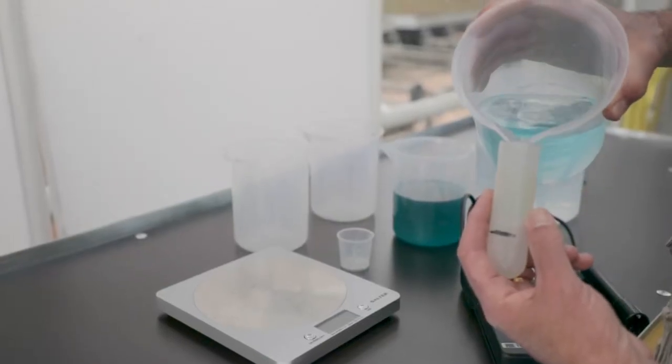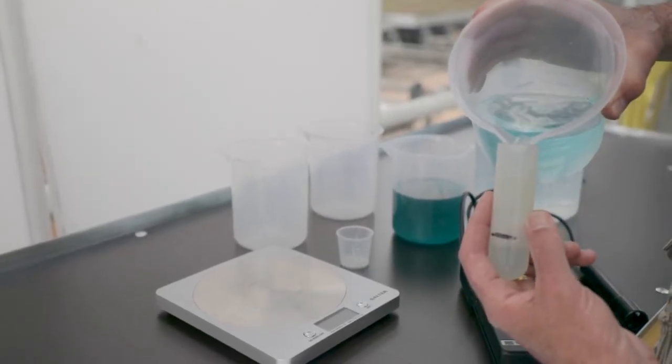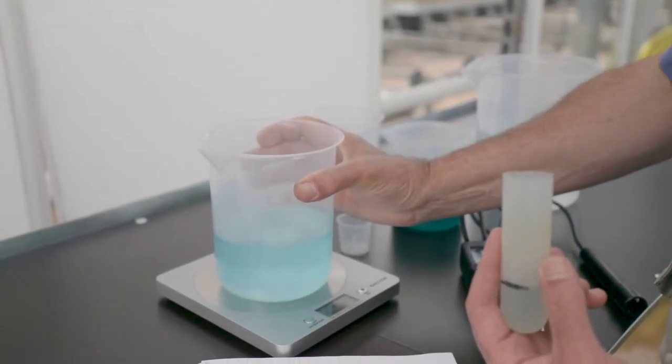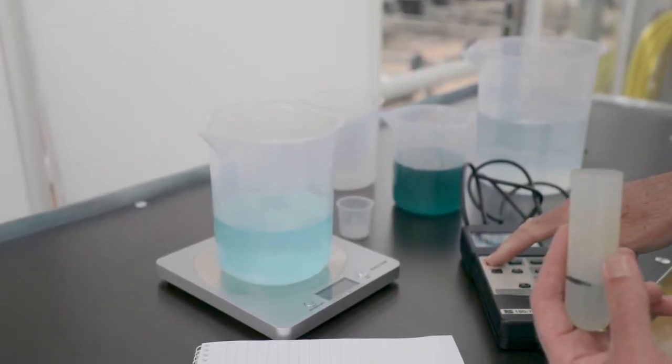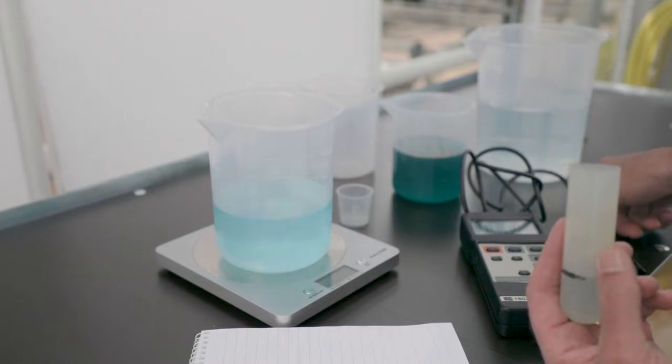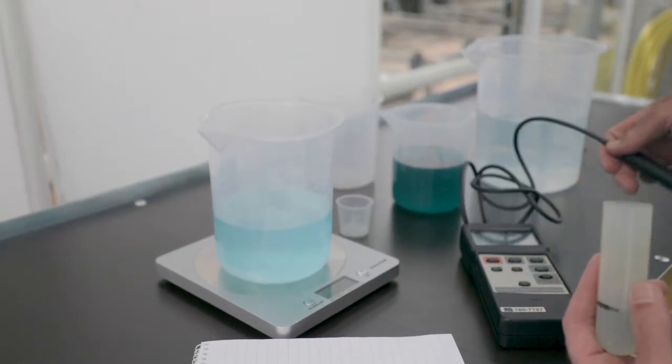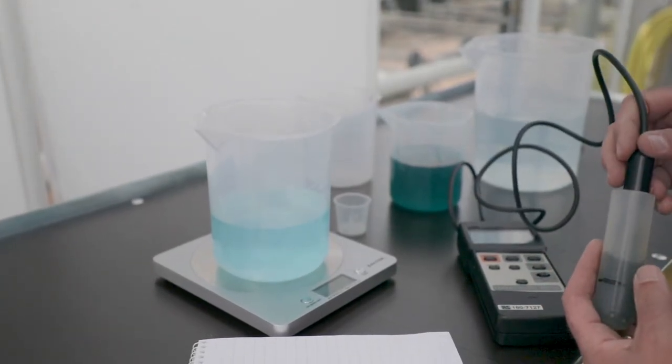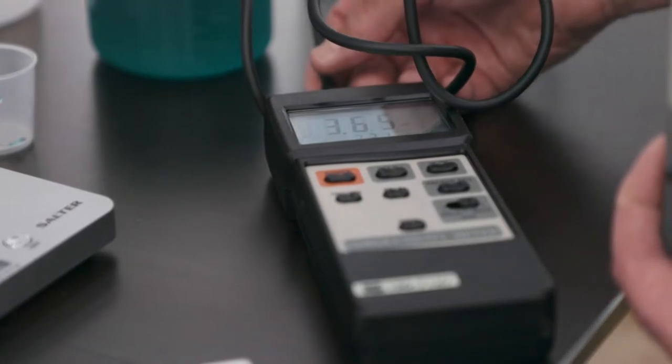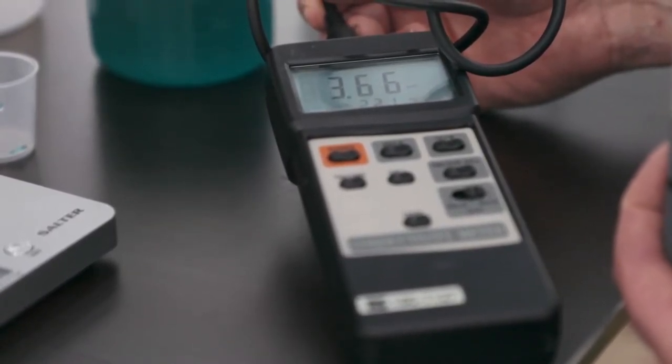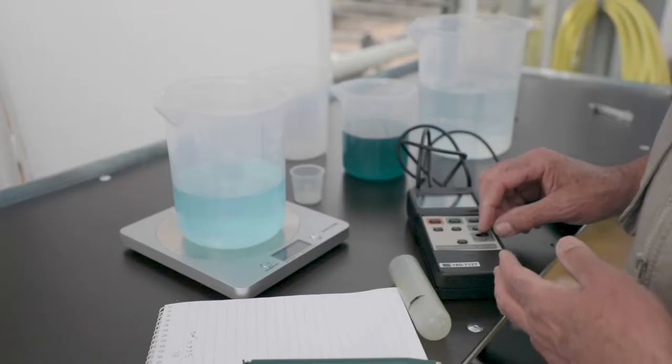We now have a one in fifty diluted solution and what we're going to do now is just measure the conductivity of this solution which will give us our first calibration point. Take a small amount of the actual diluted solution. This gives us a reading of three thousand six hundred and sixty microsiemens and that's your most concentrated level.